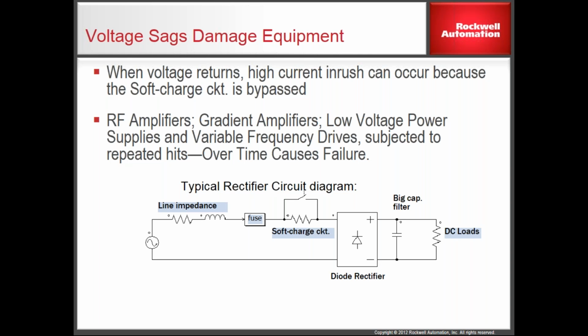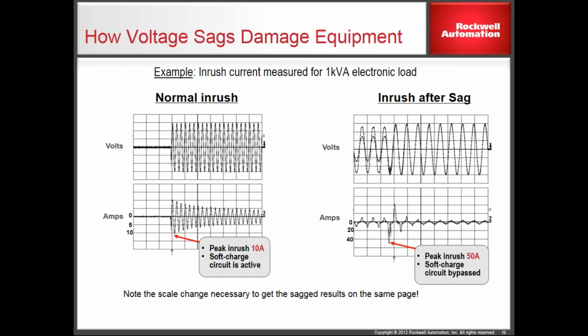So the current inrush that happens at the back end of the voltage sag has nothing to manage it. The inrush currents you'll see are between 5 and 17 times the inrush current you get at startup. In some cases the power supplies are just going to blow; in other cases it shortens their life.